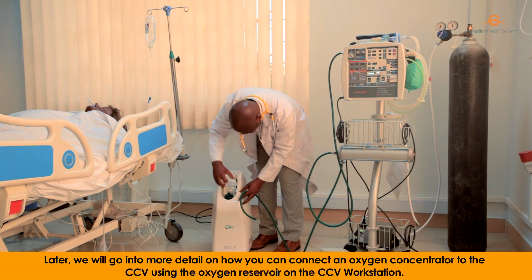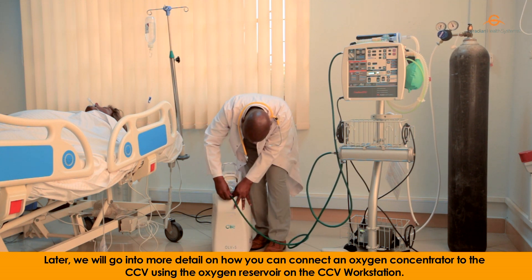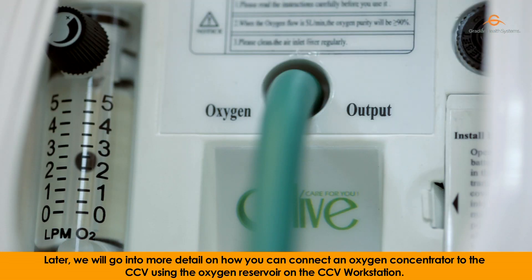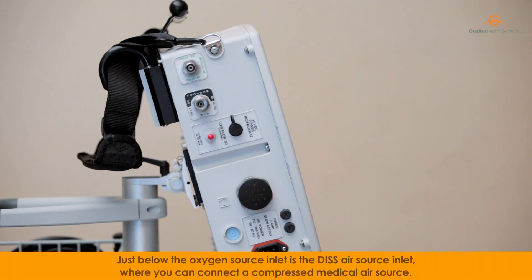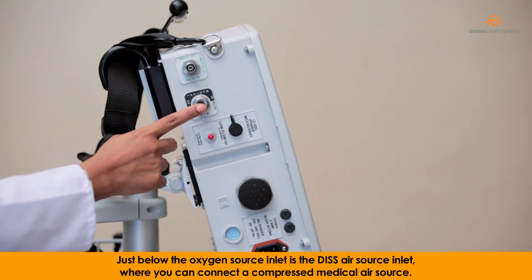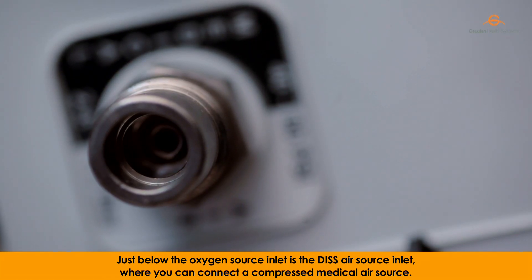Later, we will go into more details on how you can connect an oxygen concentrator to the CCV using the oxygen reservoir on the CCV workstation. Just below the oxygen source inlet is the DISS air source inlet, where you can connect a compressed medical air source.